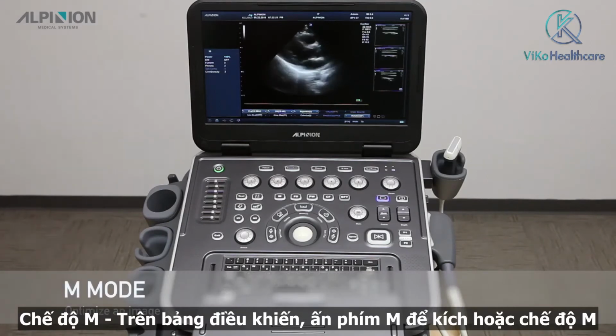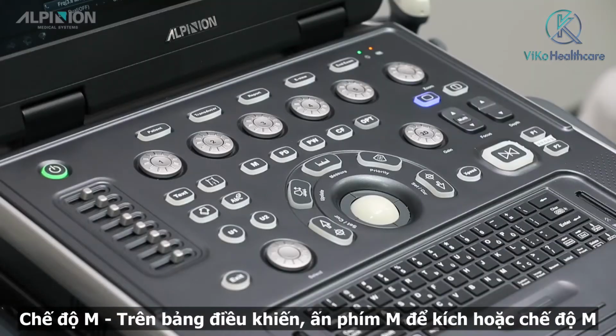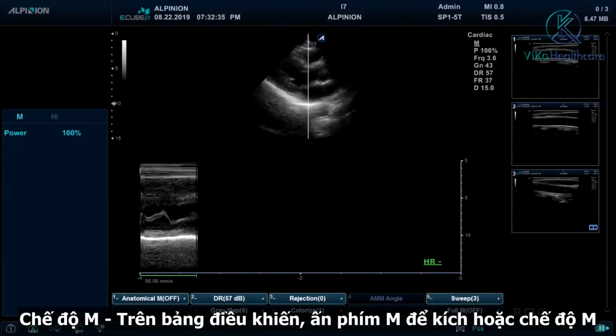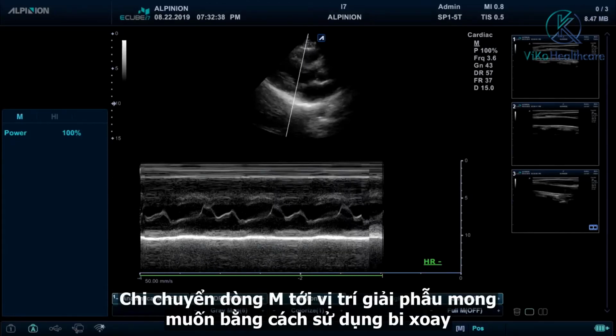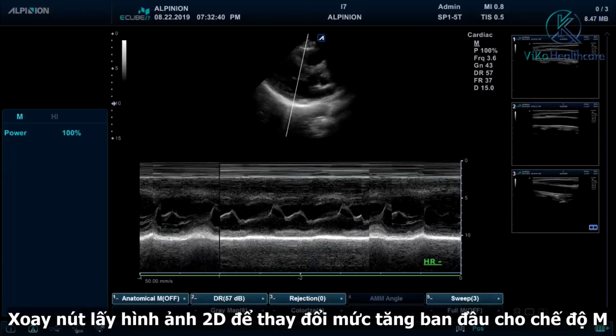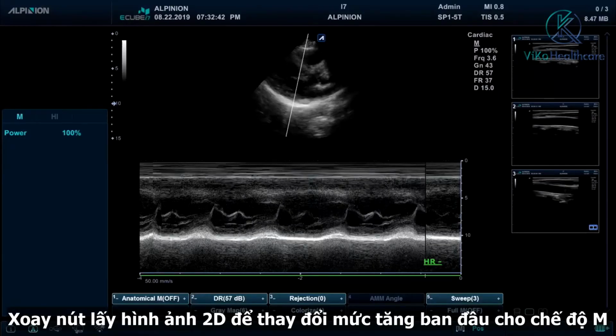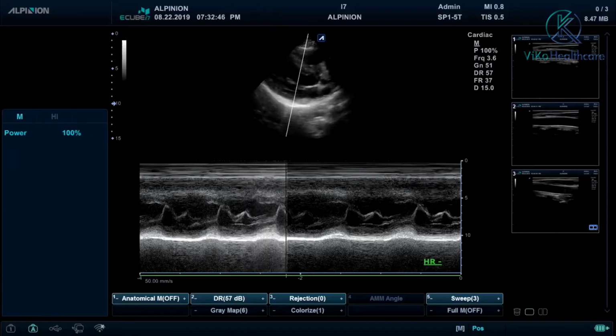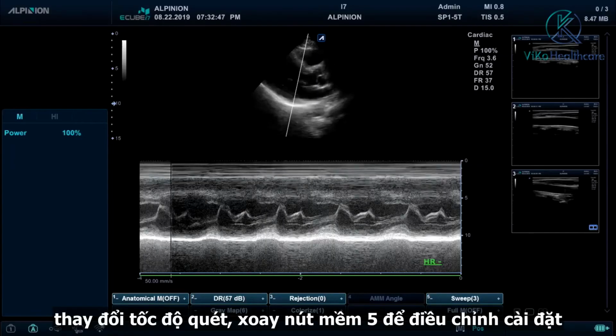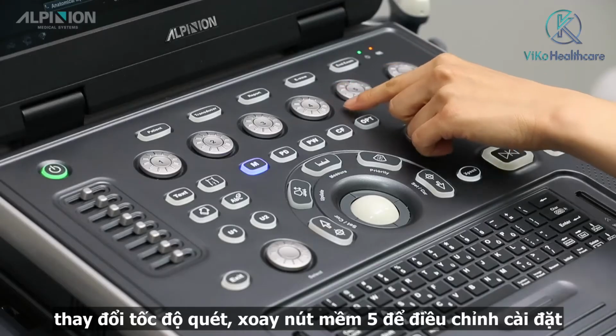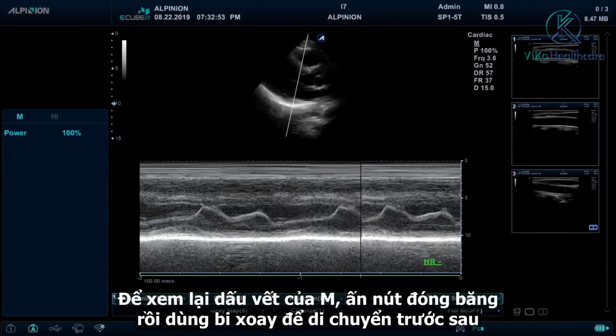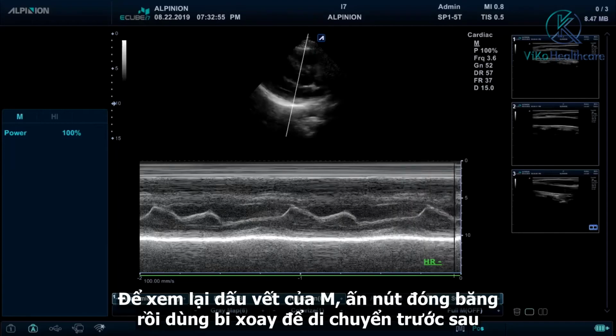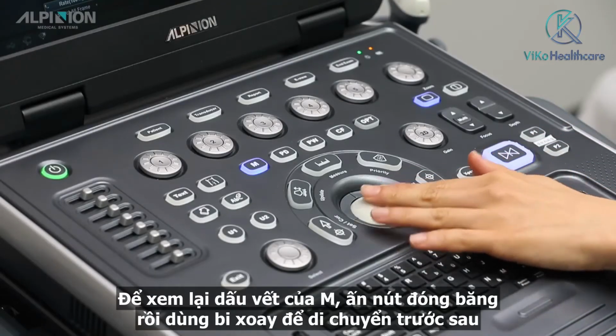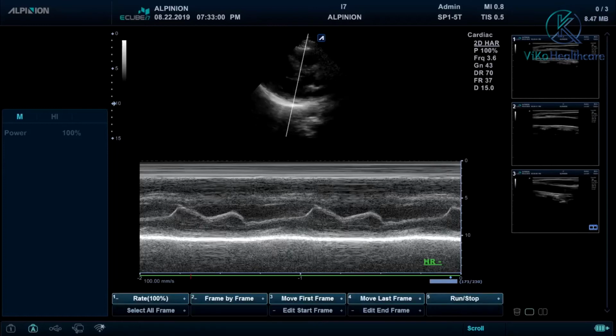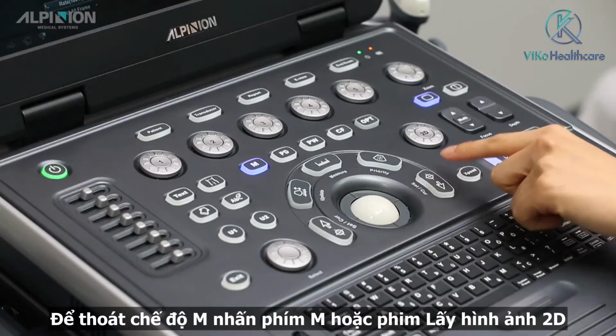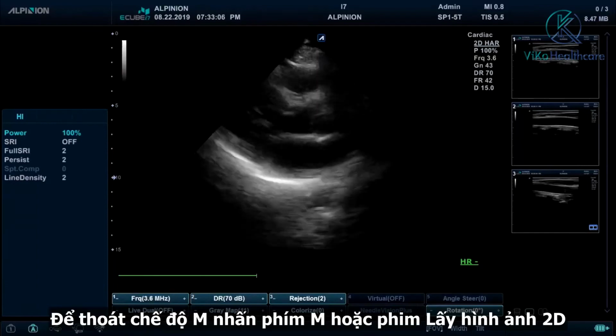M mode. On the control panel, press the M key to activate M mode. Move the M line to the anatomy of interest by using the trackball. Rotate the Gain 2D key to change the initial gain for M mode. To change the sweep speed, rotate soft key 5 to adjust the setting. To review the M mode trace, press the freeze key and use the trackball to scroll forward or backward. To exit M mode, press the M key or the Gain 2D key.